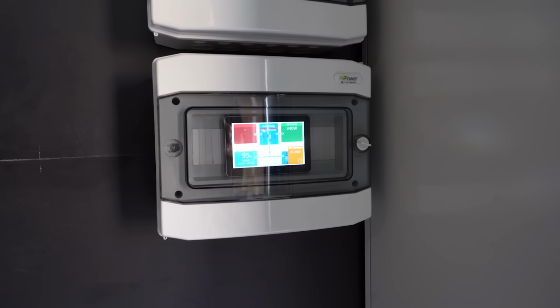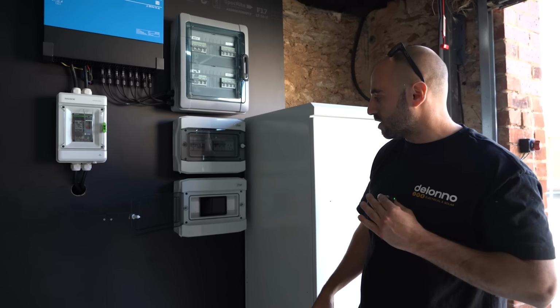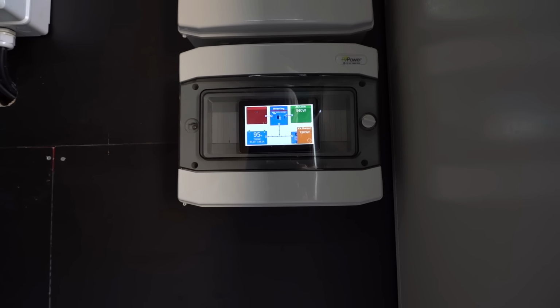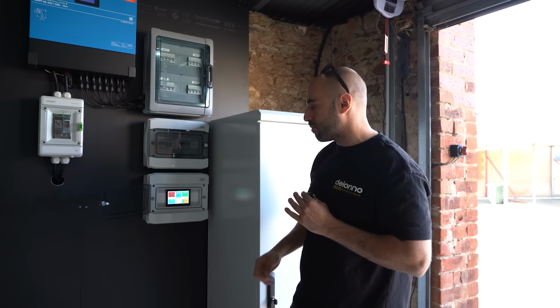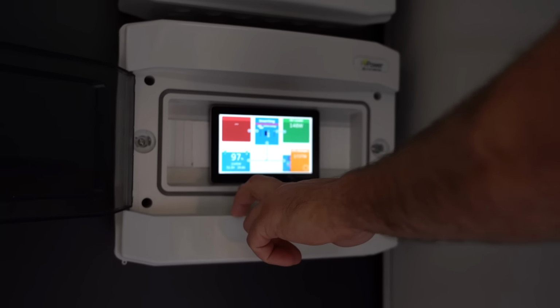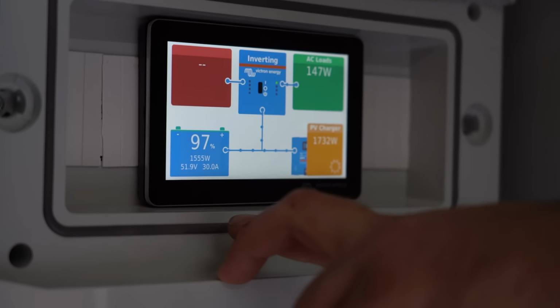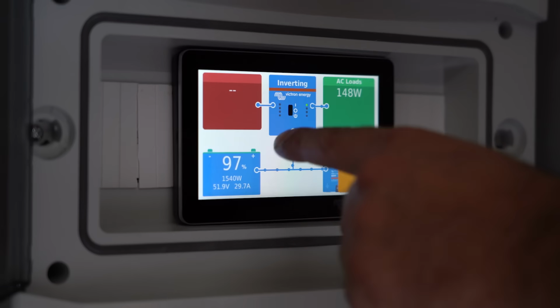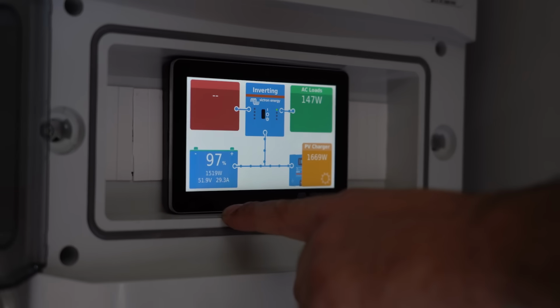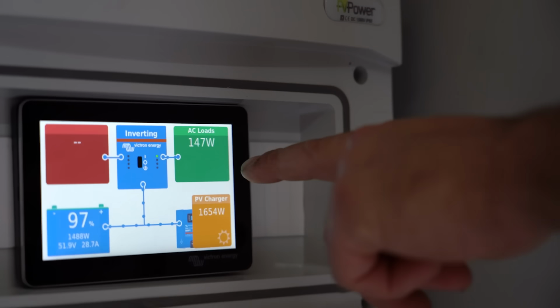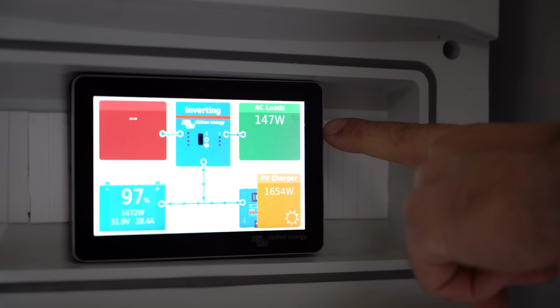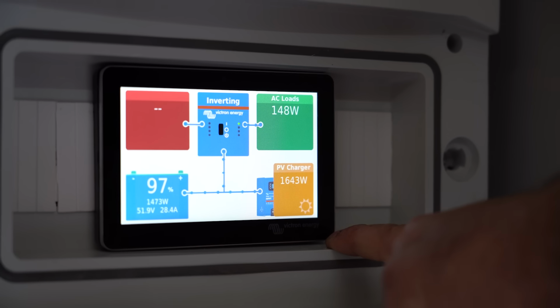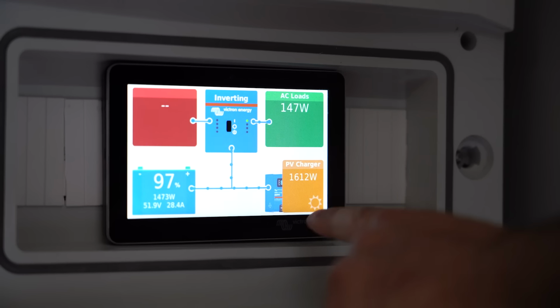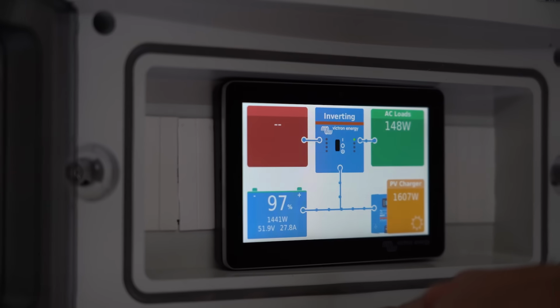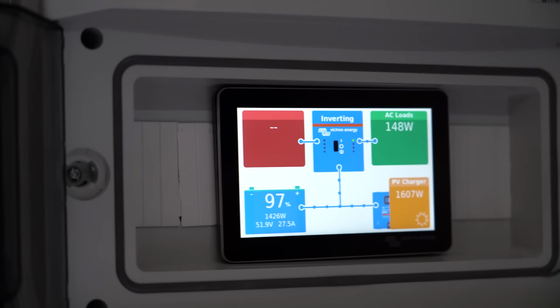What we have to sort of see how the system's doing, like on every Victron system, we integrate a Cerbo GX control into it. So we've got the GX Touch 50, the smaller unit with a Cerbo GX behind the enclosure. This keeps it super neat. We can see PV charge coming in, so we're at about 97%. Because we have a managed battery with the Pylontechs, we can see through comms where the batteries are at. So we're at 97% here, and it's accepting 1.5 kilowatts. We can see the loads throughout the property are quite low, there's no one here at the moment, only 147 watts of power, and then we can see how much power is coming from our MPPT being converted to our battery stack. This is really good, and in this top left-hand corner we'll see a gen input when we turn that on. So it's really good to be able to get some control and see how everything's working.